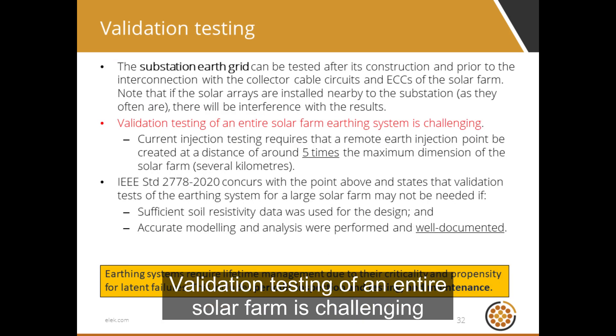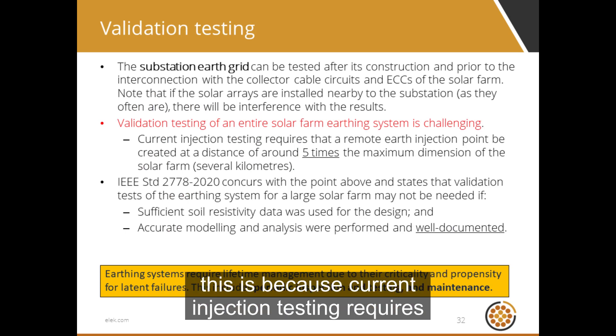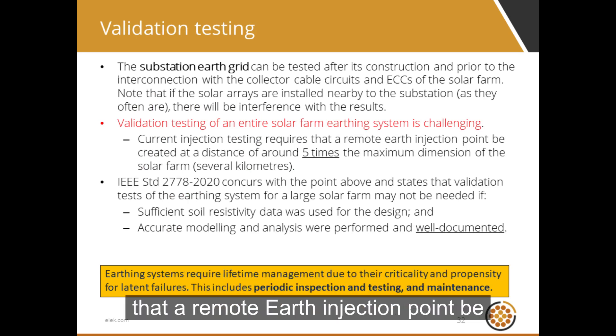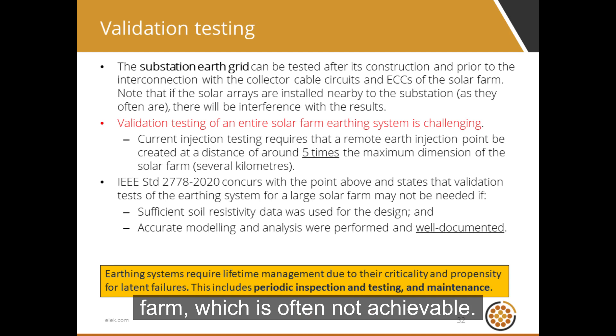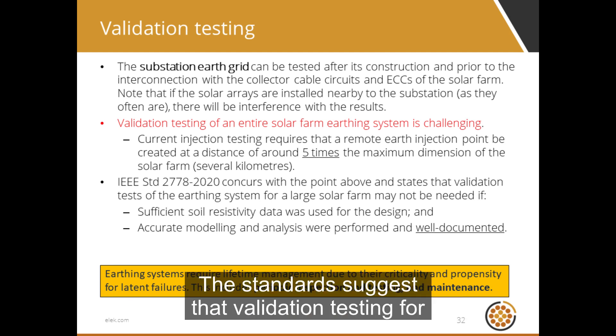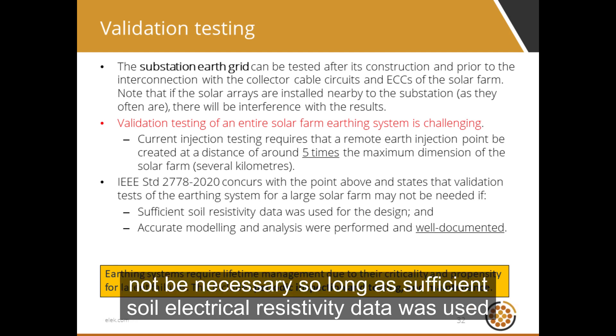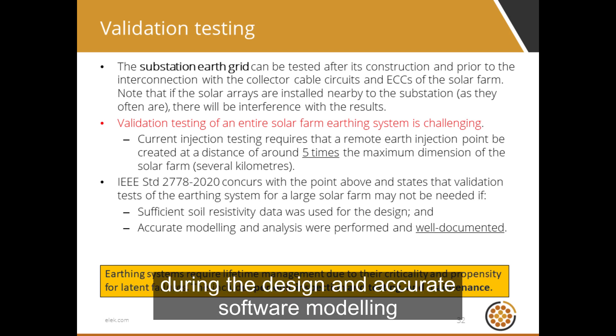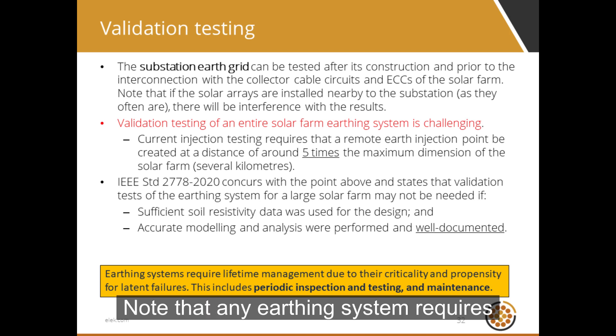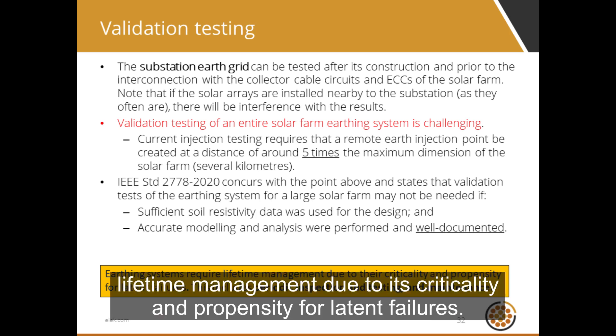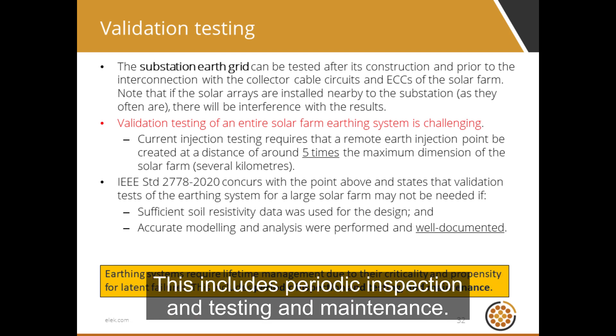Validation testing of an entire solar farm is challenging because current injection testing requires a remote earth injection point at a distance of around five times the maximum dimension of the solar farm, which is often not achievable. The standards suggest that validation testing for the earthing systems of the solar farm may not be necessary so long as sufficient soil electrical resistivity data was used during the design, and accurate software modeling was performed and is well documented. Note that any earthing system requires lifetime management due to its criticality and propensity for latent failures, including periodic inspection, testing, and maintenance.